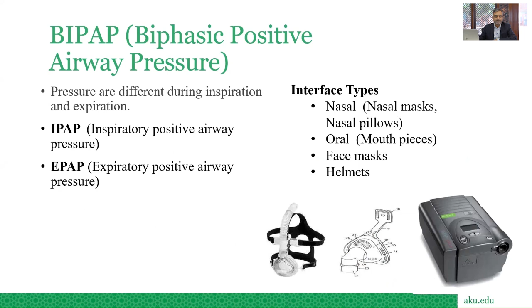So BiPAP, usually we start with settings of 8/4. Maximum IPAP we go up to 20 to 25 centimeter of water. EPAP is 10 to 15 depending on the condition. There are two types of machine. In one machine we connect oxygen and provide oxygen in liters per minute flow, which means that we start with 5 liters of oxygen, and depending on the condition we can go up to 10 or 15 liters of oxygen.